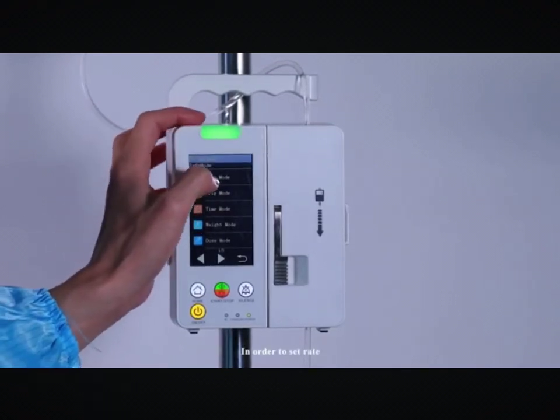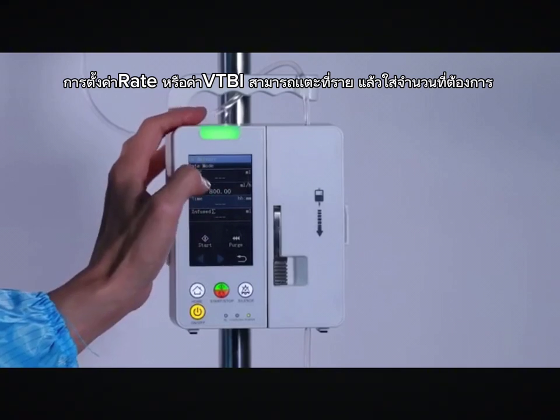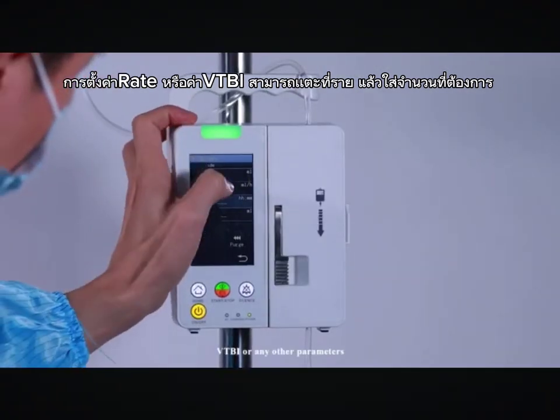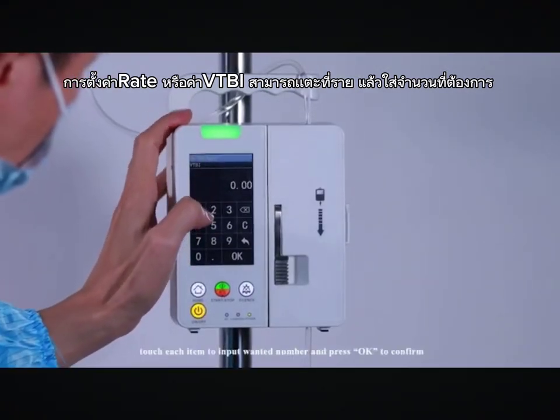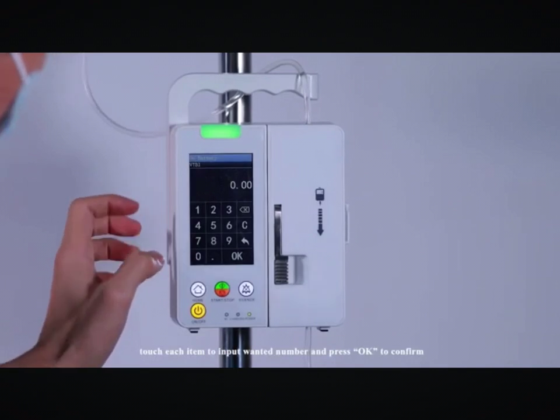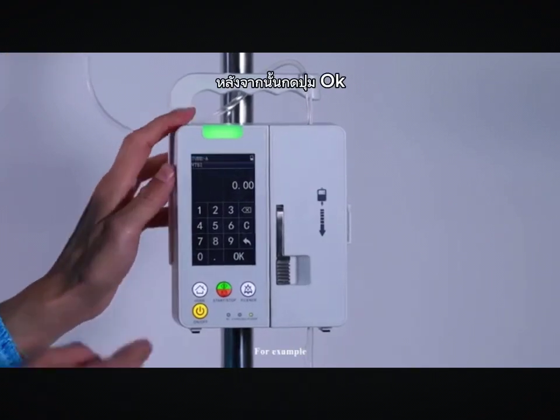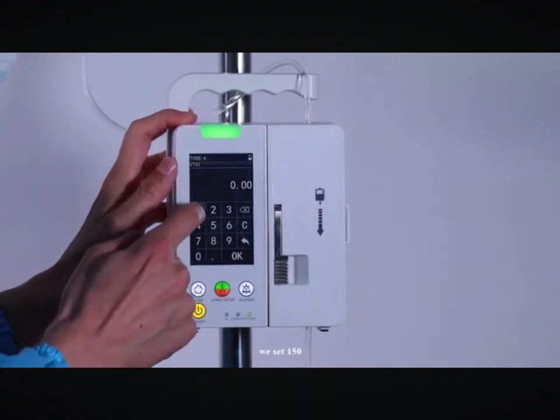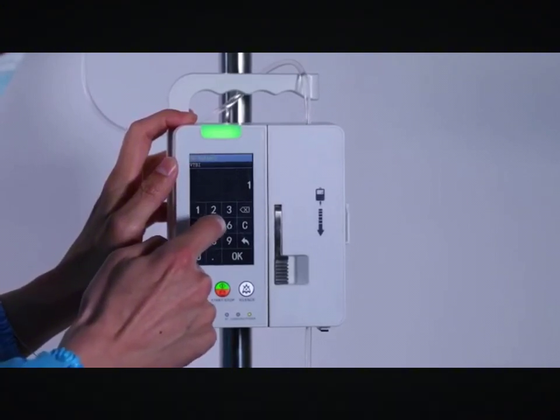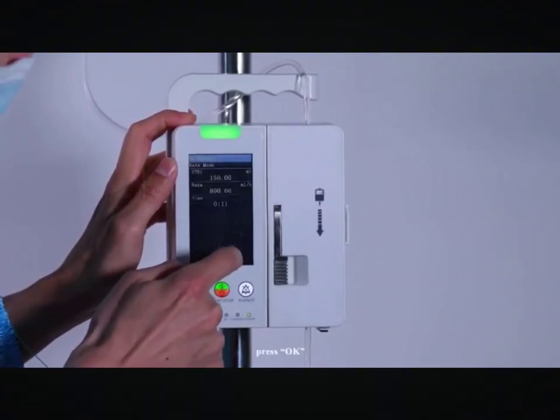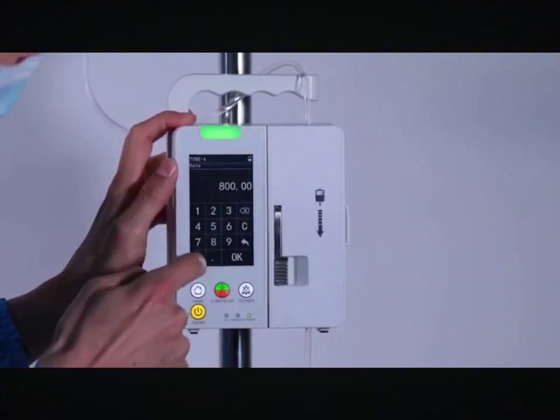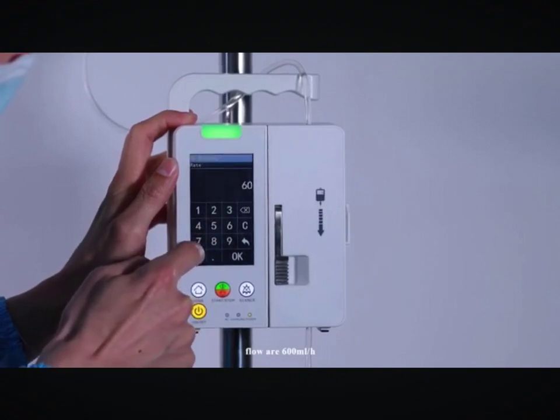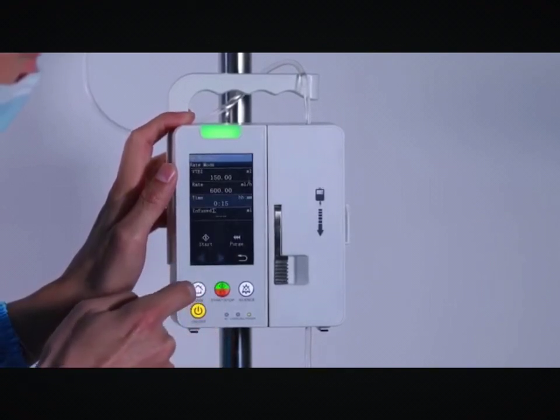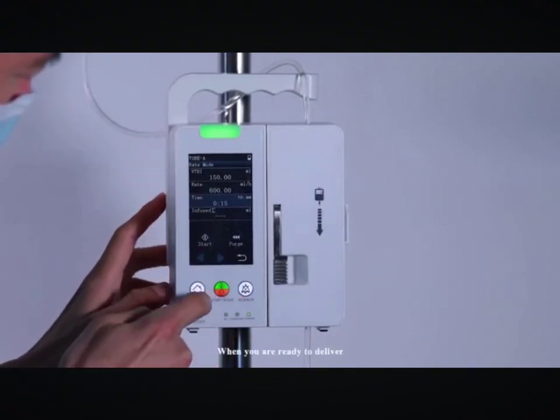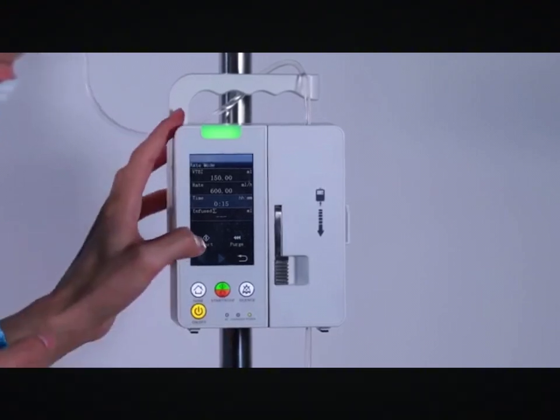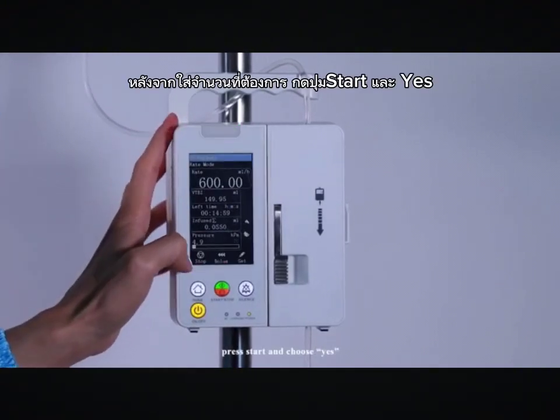In order to set rate, VTBI or any other parameter, touch each item to input the wanted number and press OK to confirm. For example, we set 150. Press OK. Flow at 600 ml per hour. Press OK. When you are ready to deliver, press start and choose yes.